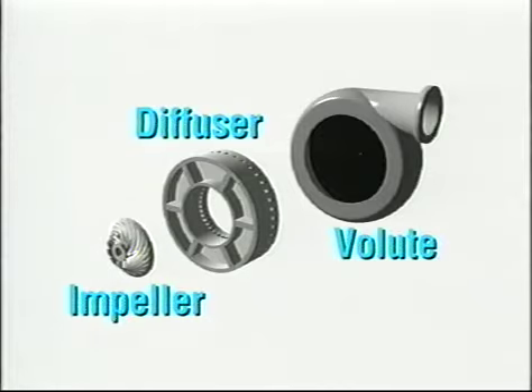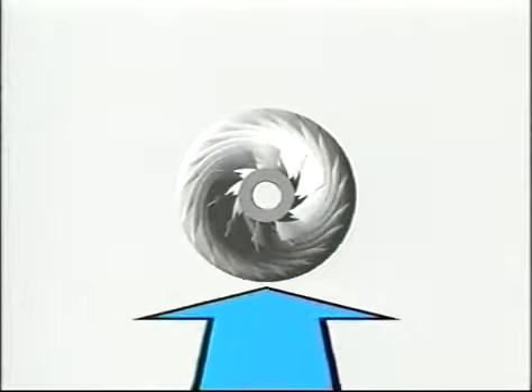Centrifugal compressors are usually driven by hermetic electric motors. The impeller is the heart of the centrifugal compressor. It is a rotating circular disc with curved blades that is driven at high rotational speed by the electric motor. As the impeller rotates, it moves the refrigerant vapor from its suction opening in the center to its outer edge by centrifugal force. The vapor enters the suction at a relatively low velocity and leaves the outer edge of the impeller at a high velocity. In other words, the impeller transfers its rotational energy to the vapor.